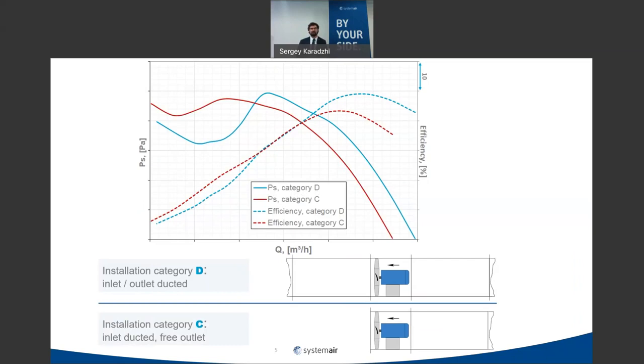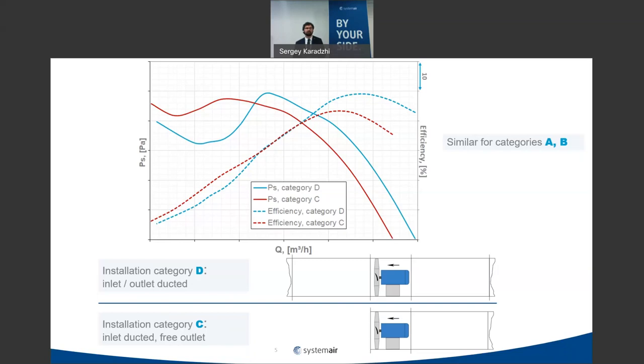This difference occurs because when there is a duct on the inlet, the velocity profile is already developed with boundary layers — low velocity near the walls and high velocity in the middle — and this profile enters the impeller differently than with a free inlet. Similarly, on the outlet, the twist in the airflow causes air to move closer to the wall, creating higher pressure losses compared to a free outlet where air spreads into the environment.